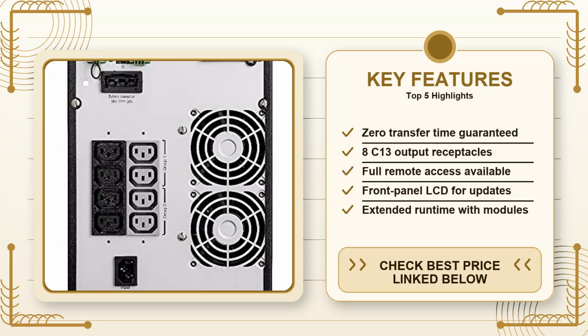In my test, when I added a 400W printer onto the same load bank as the workstation, the UPS reported a reduced remaining runtime almost instantly. It wasn't a failure, just the UPS being honest about its capacity. That's something you have to factor into planning if you have a mixture of devices with wildly different power profiles.